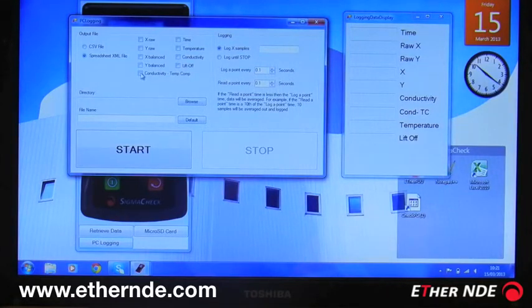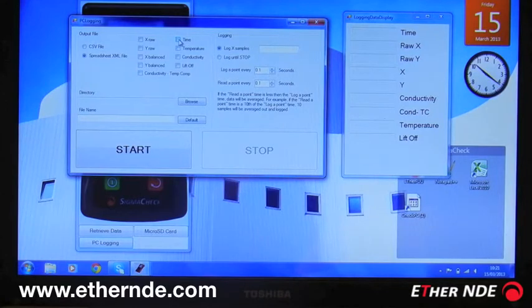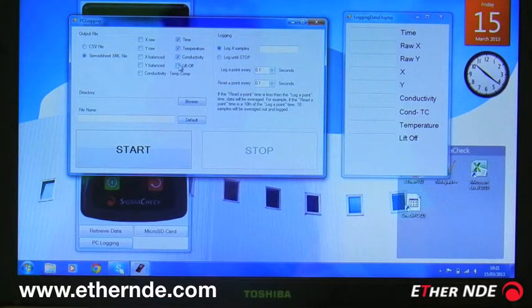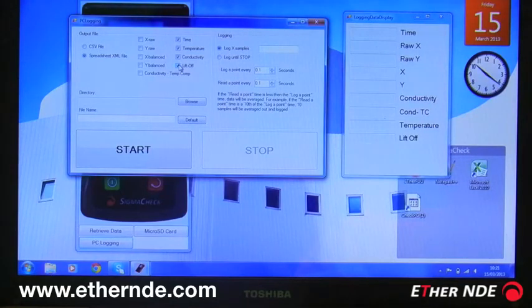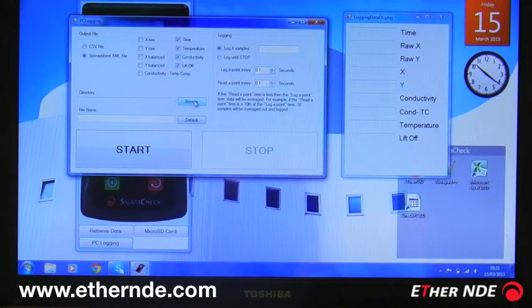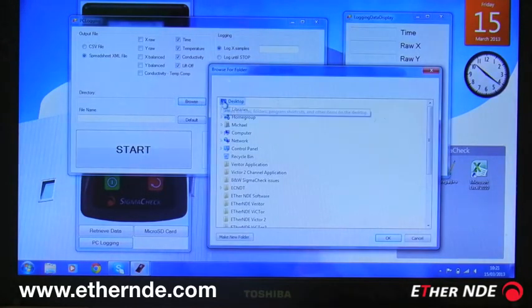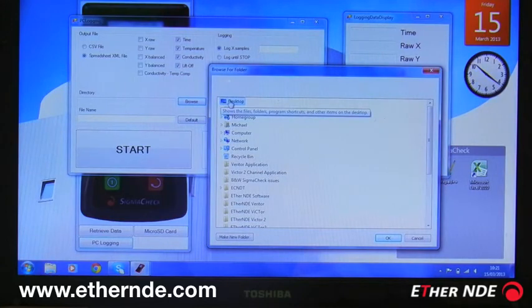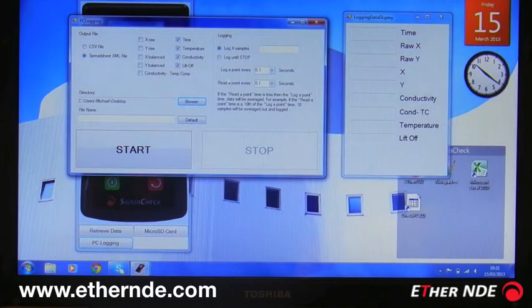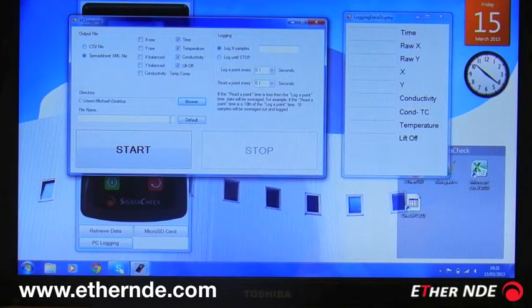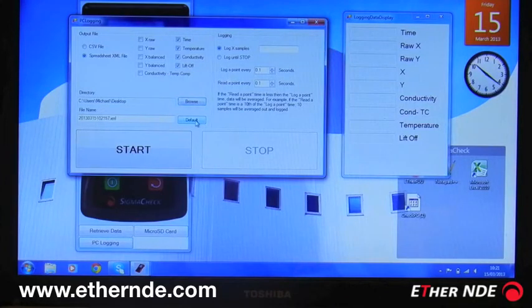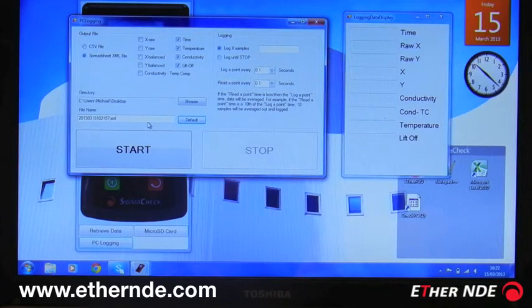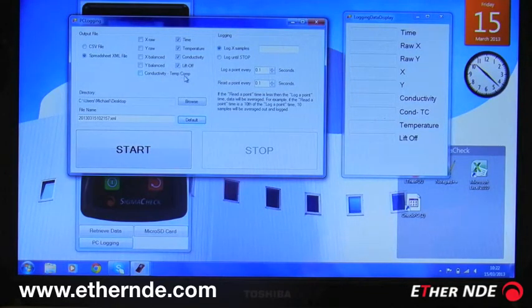I can then choose the data that I require to log from the SigmaCheck. For this example, we should log the time, temperature, conductivity, and the liftoff. Now I should browse to a location to save the file. The desktop is highlighted. I can enter a file name or I can just click default and it will create one based on the current time and date.